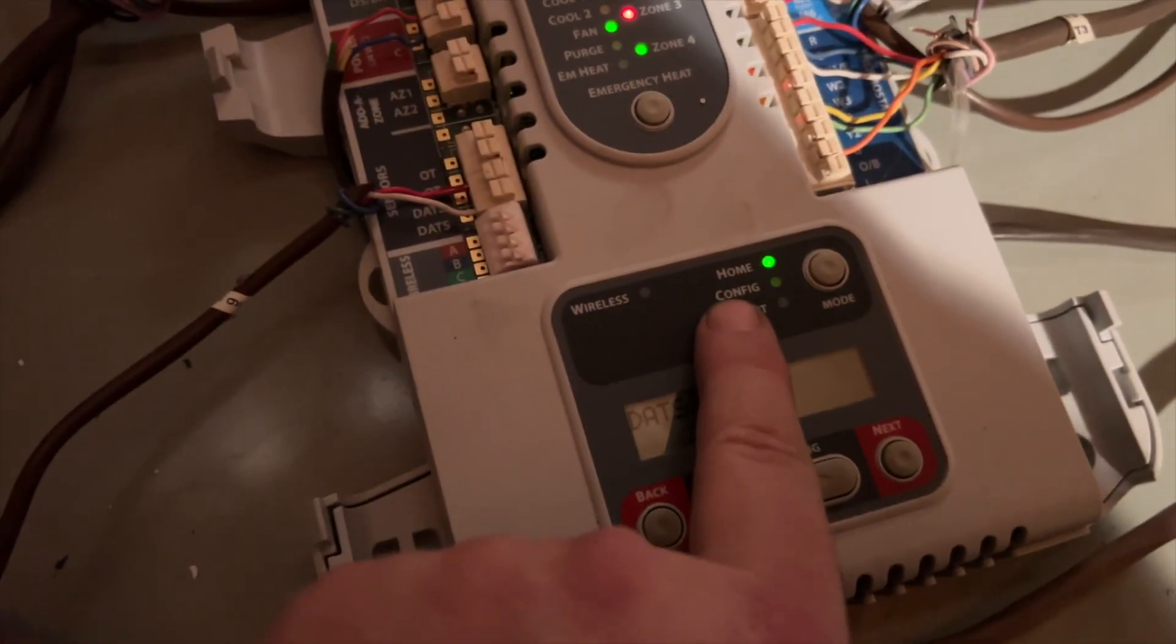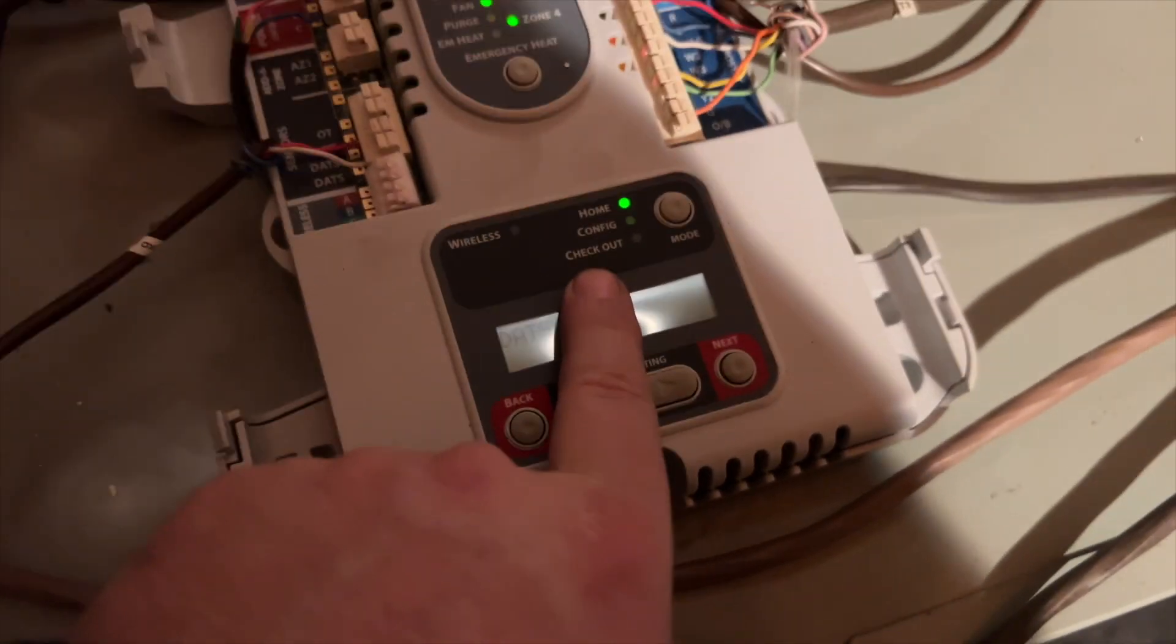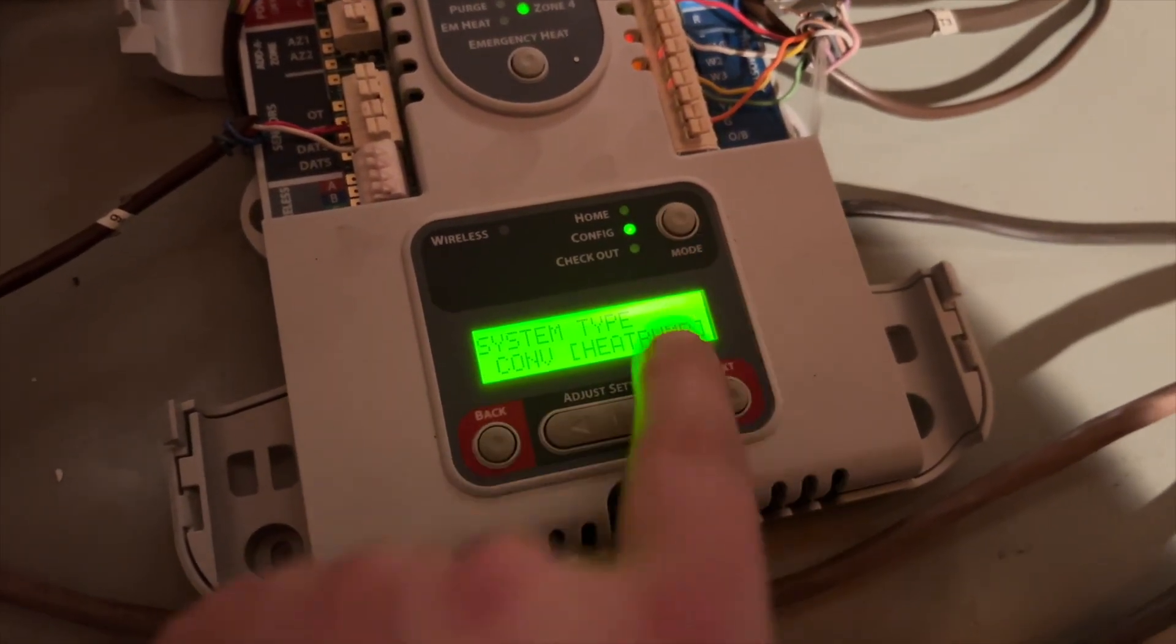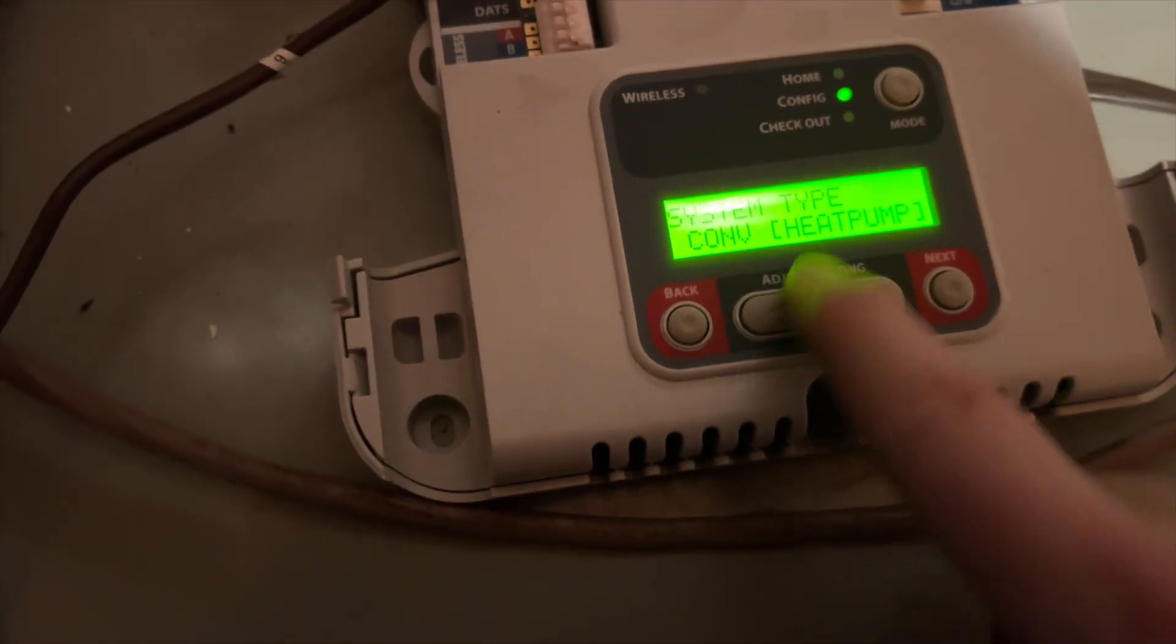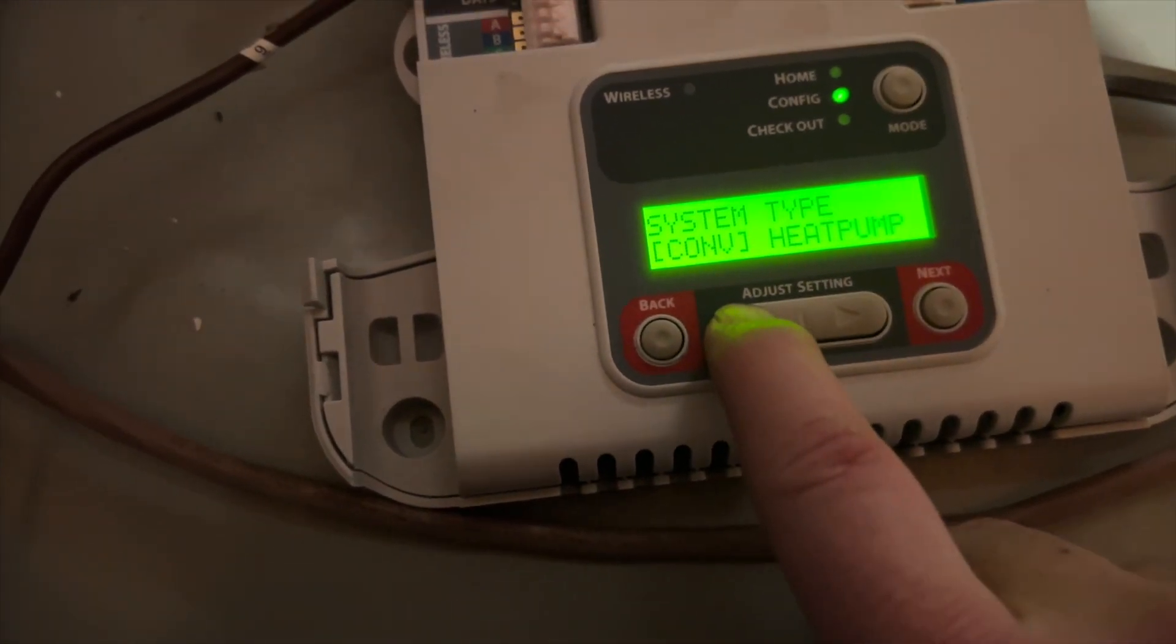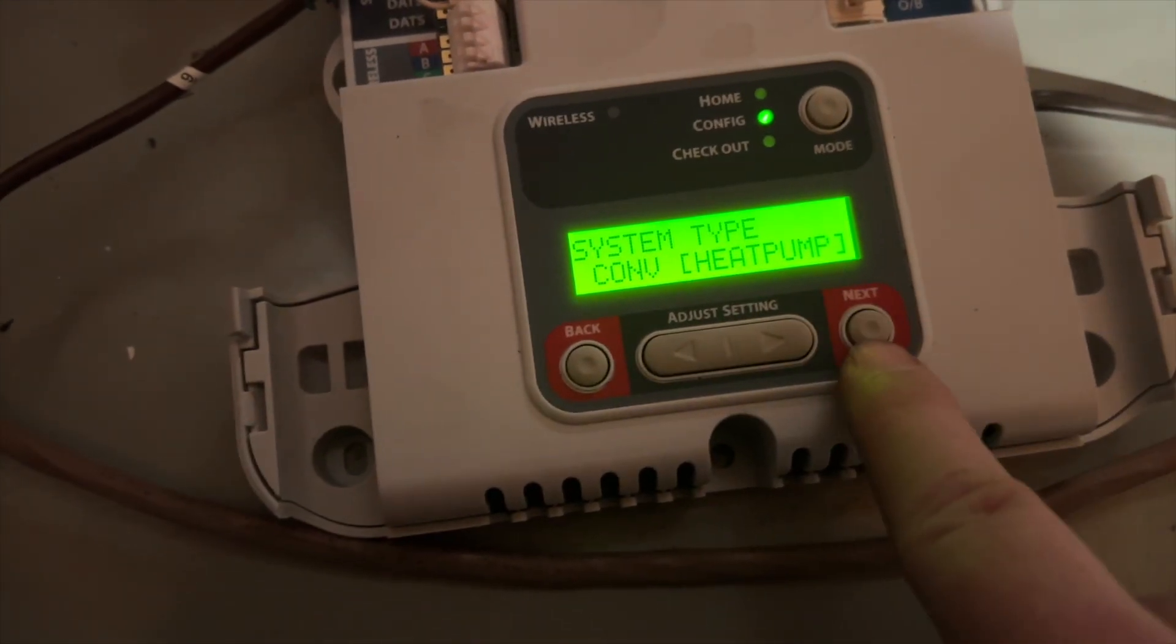Right here we can see we're at home - that's basically normal operation mode. Configure gives us our settings. And checkout basically puts it in test mode. So if we hit this button here, which is our mode button, it takes us into configuration. So here we can change our settings. We're not going to, but this is a heat pump. You can see the brackets are in heat pump. If we wanted to change that, we use these two arrows here. Now it's conventional, now it's heat pump. We want to go to our next setting, we hit next or we can go back.